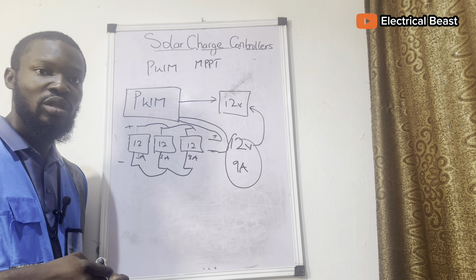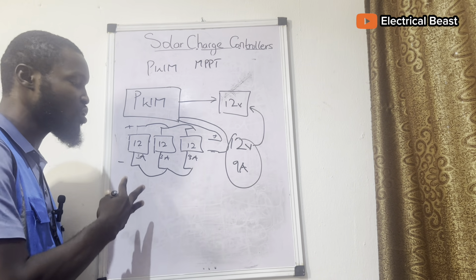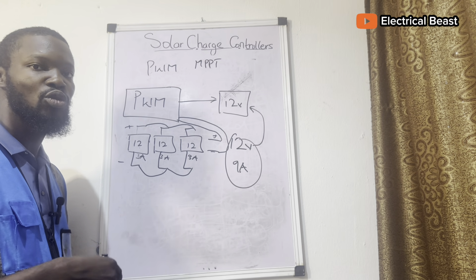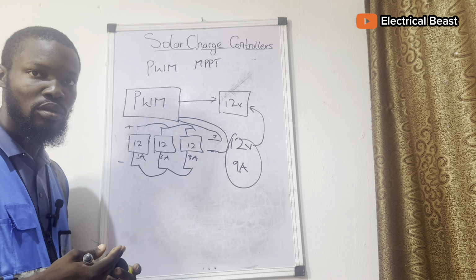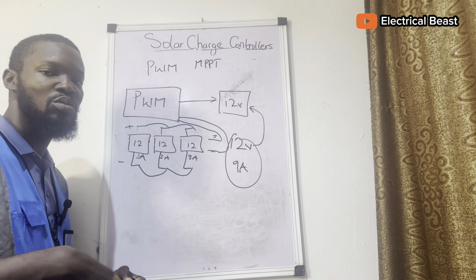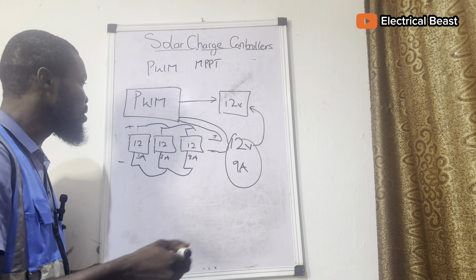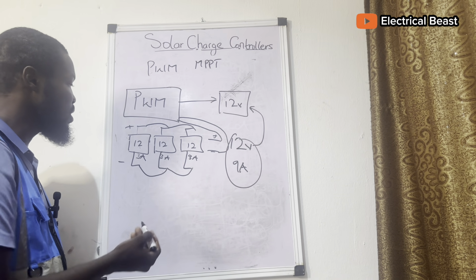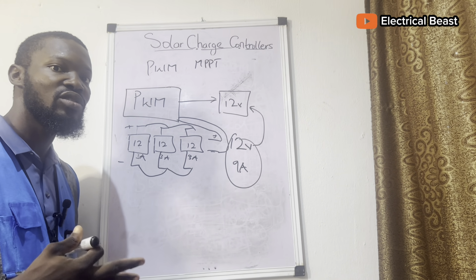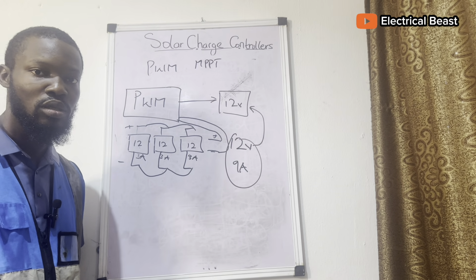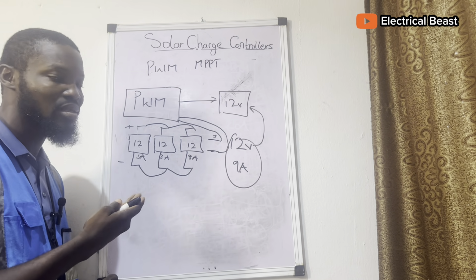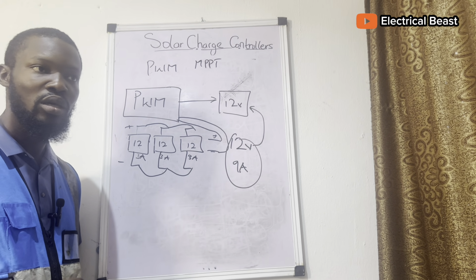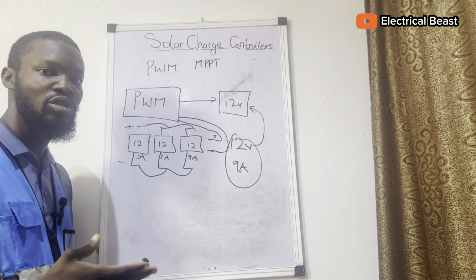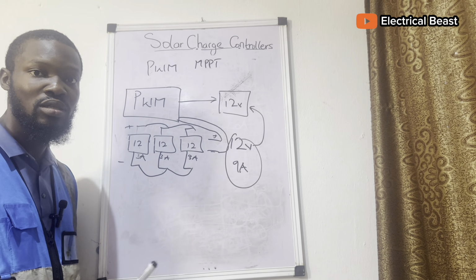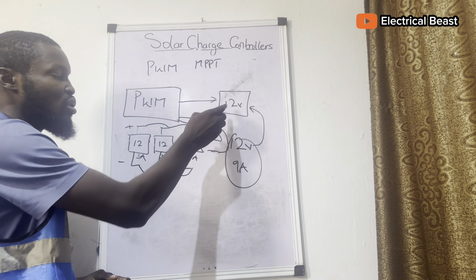For PWM controllers, you need to make sure that the voltage of the battery is equal to the voltage of the panel connection. If the voltage of the panel connection is more than the voltage of the battery, the controller will only take the voltage that it needs - the excess voltage will be counted as losses. For you to be able to maximize the use of your PWM controller, you need to make sure that the voltage of the connection for your panels is equal to the voltage of the battery.